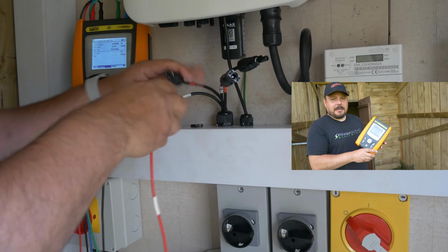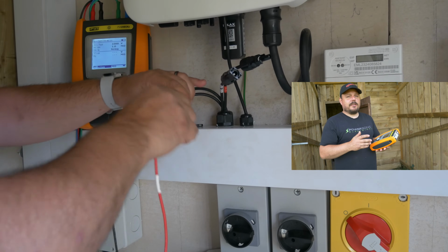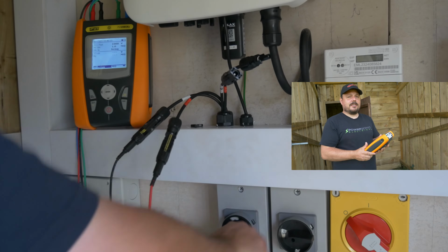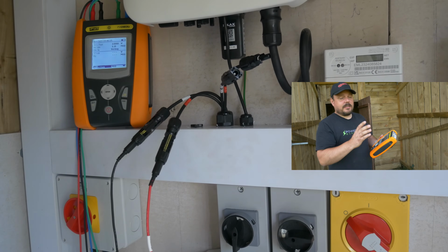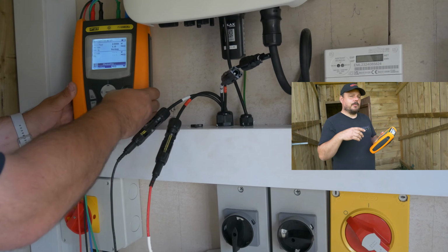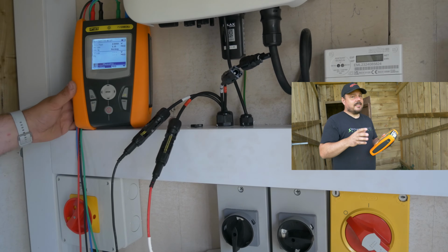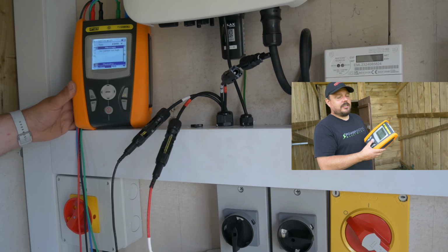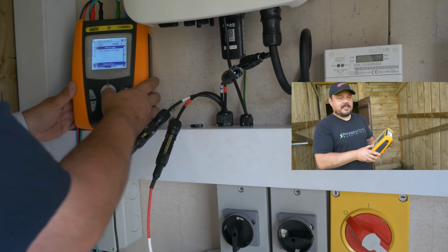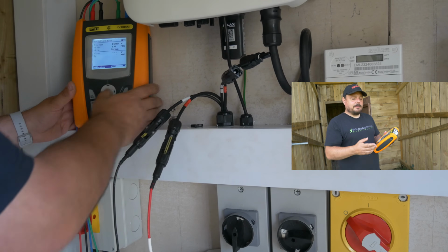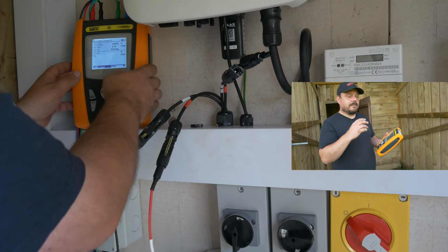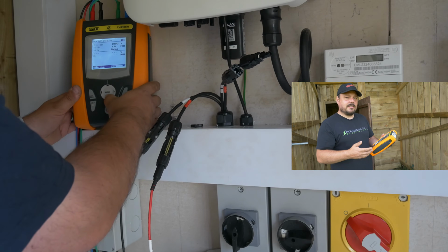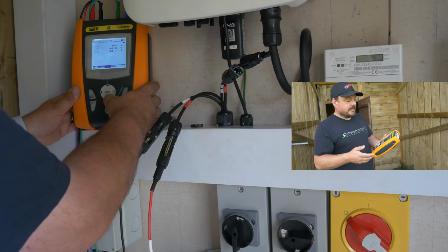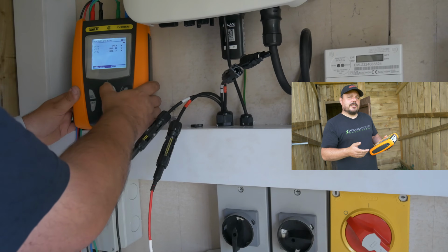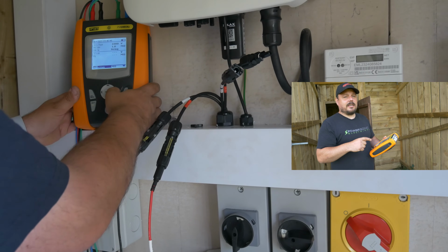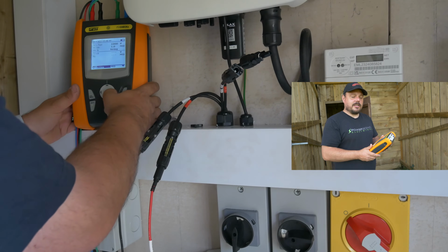Okay, so we've also got the PVcheck. This is in essence the multifunction tester of solar systems. It has much of the same features as the IsoTest, but with a few important added extras and differences. So with this one, you can do what's termed the IVCK test. And basically that's a system test, so it'll run through and do the voltage measurements, the current measurements in the system. It'll take an irradiance value, do your insulation resistance measurement, and also check that earth bond if one is in place onto the array frame.